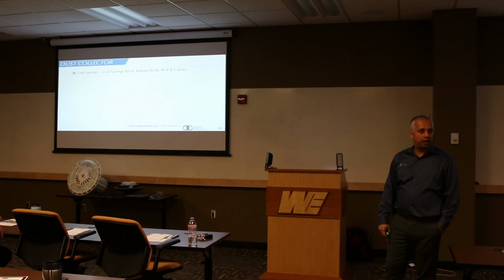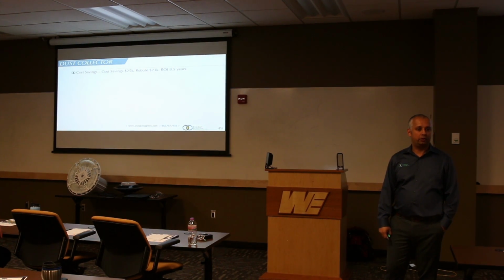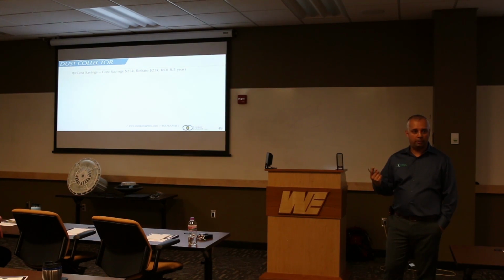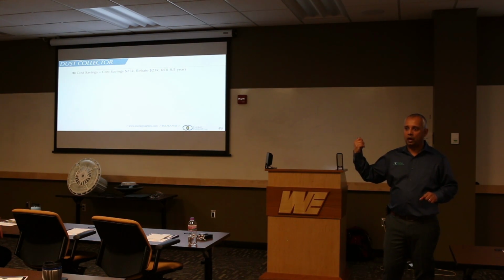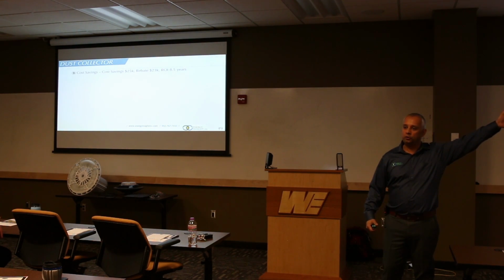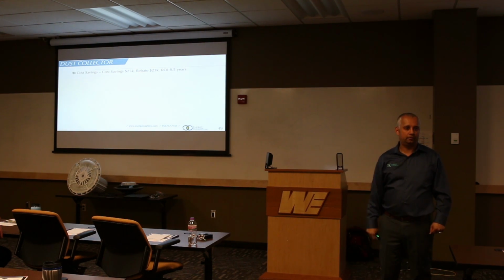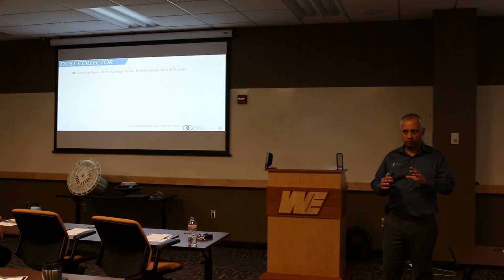Dust collectors, again, great candidates for variable frequency drives. Dust collectors are notorious for running those motors all the time. Plus, they take your conditioned air out of your space, and out it goes, because then your makeup air unit is trying to make that up. And in winters, if people are complaining it's really, really cold, first thing we do is look for the dust collector. Install variable frequency drives. If you can slow down the motor, you will save energy.